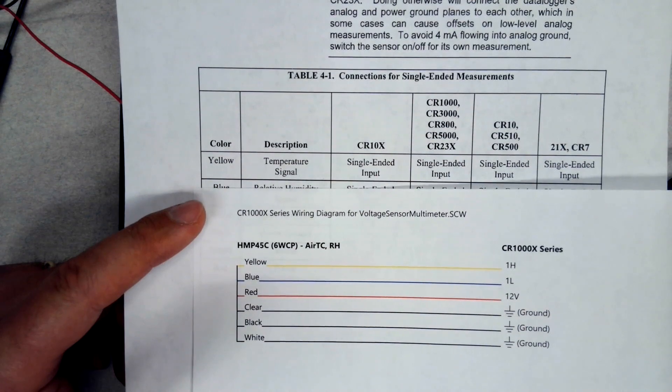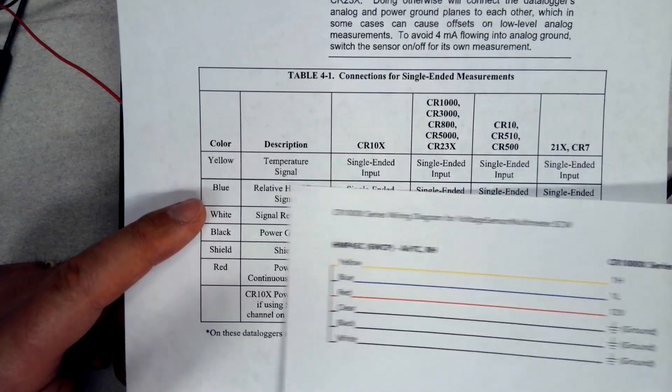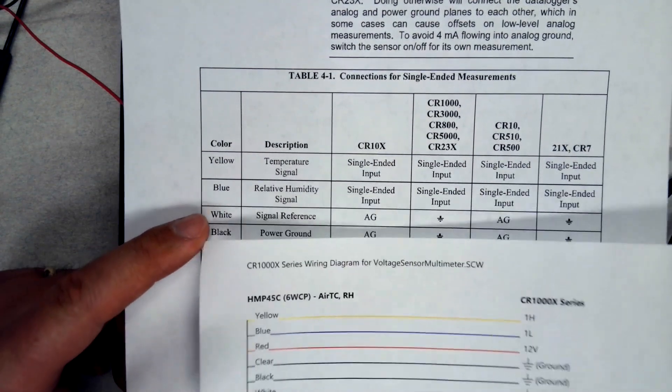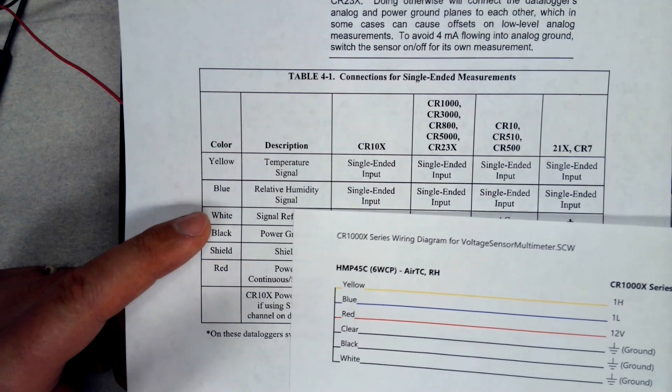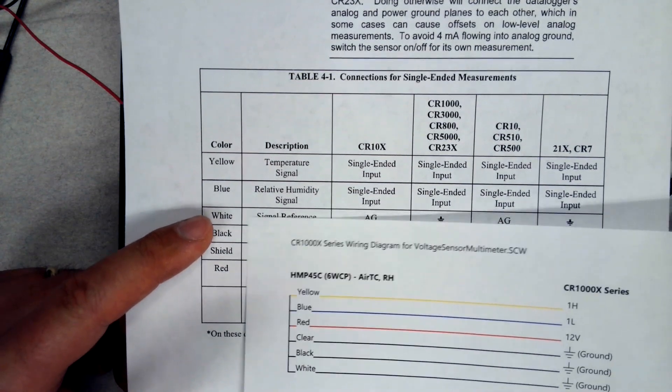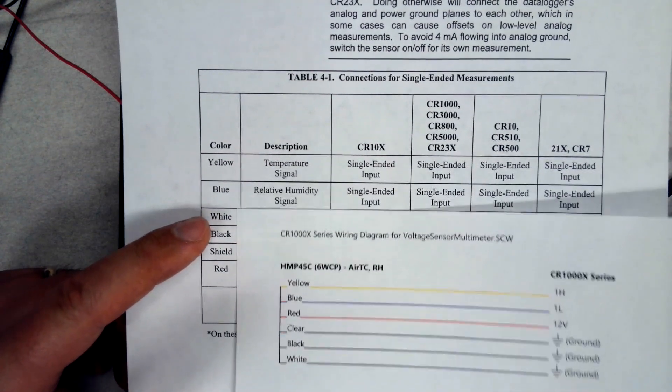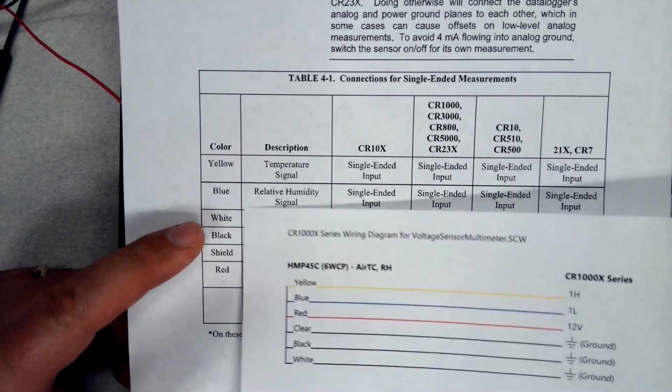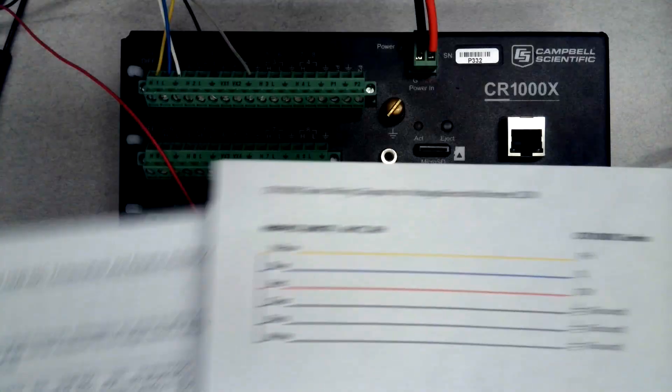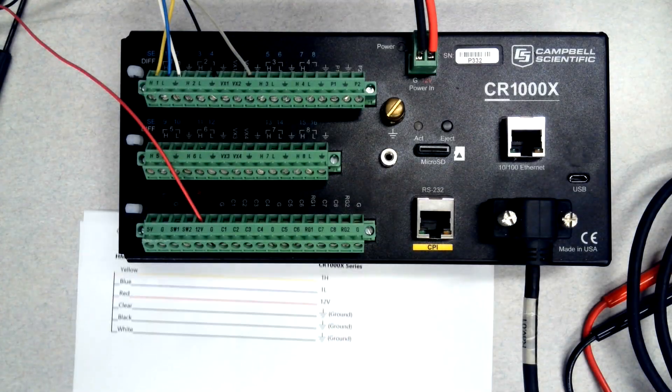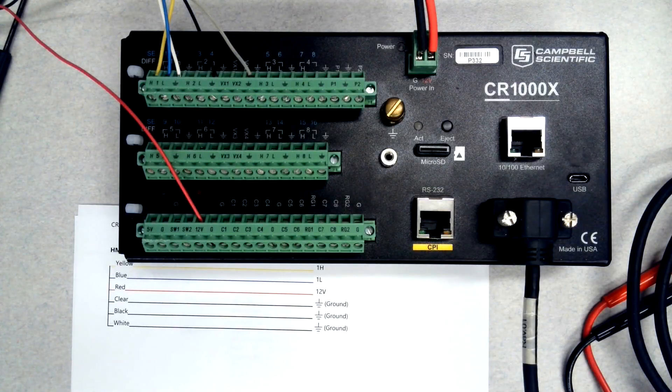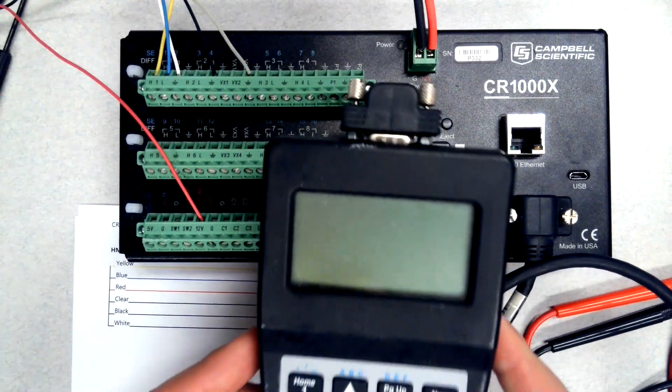I'm interested in the yellow signal. In this sensor, the yellow wire is the temperature signal, and the blue wire is a humidity signal. So I'm going to be looking at the voltages on these two, and that's going to be referenced to one of the grounds.